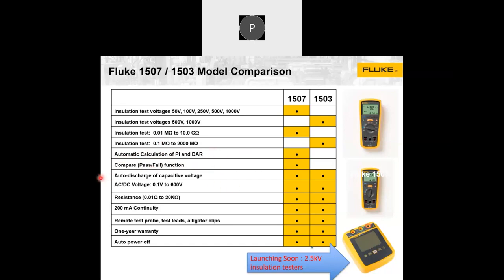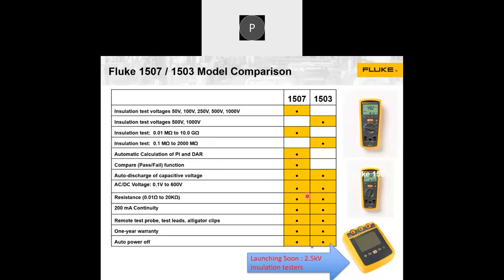Both of these models come with auto discharge, so they will not hold any current after high voltage testing. The device under test may absorb some current, and it may give a shock if the tester doesn't have auto discharge. That is why you need to be very careful when choosing high voltage testers or insulation testers, otherwise you may end up getting shocks.